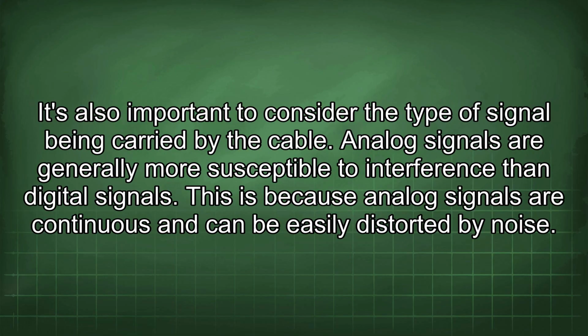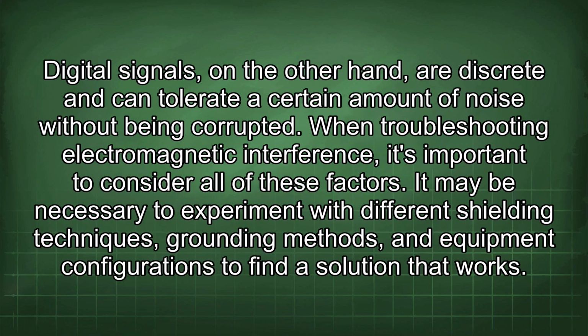It's also important to consider the type of signal being carried by the cable. Analog signals are generally more susceptible to interference than digital signals. This is because analog signals are continuous and can be easily distorted by noise. Digital signals, on the other hand, are discrete and can tolerate a certain amount of noise without being corrupted. When troubleshooting electromagnetic interference, it's important to consider all of these factors.